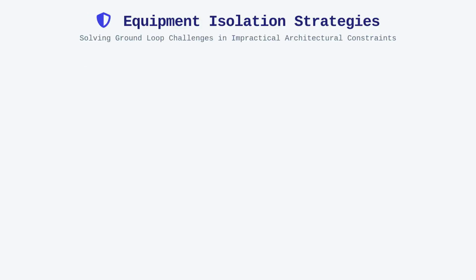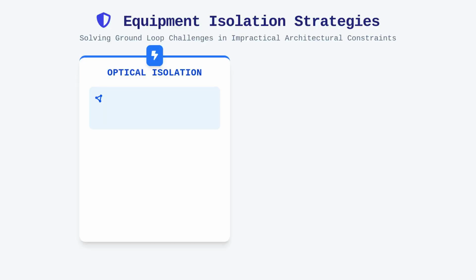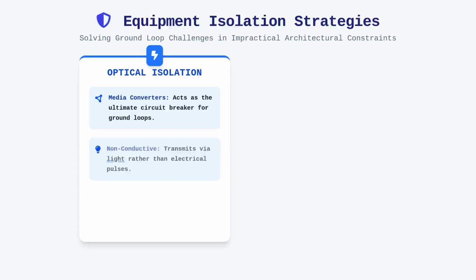When architectural constraints make a perfectly unified ground impractical, we must turn to isolation strategies to protect the equipment. Optical isolation, facilitated by fiber optic media converters, acts as the ultimate circuit breaker for ground loops. Because fiber optics transmit data via light rather than electrical pulses, the physical connection between pieces of equipment becomes fundamentally non-conductive. A fiber optic link effectively decouples the grounding domains of the two connected devices, rendering potential differences between them entirely irrelevant to the signal quality.